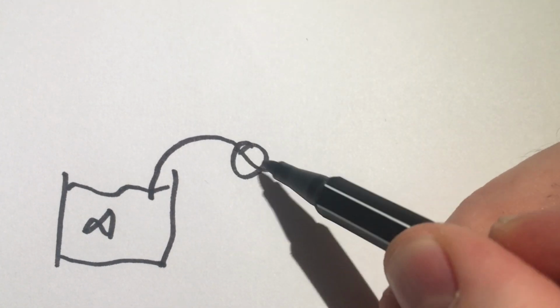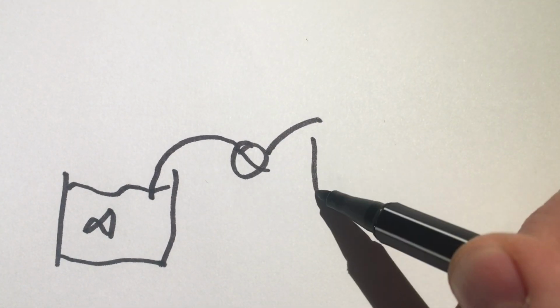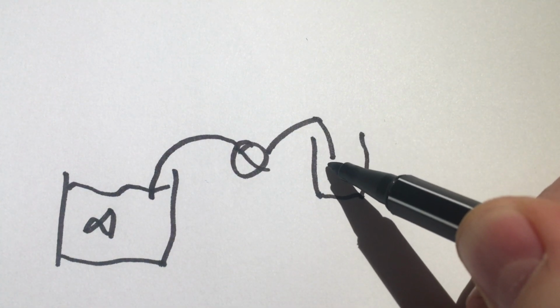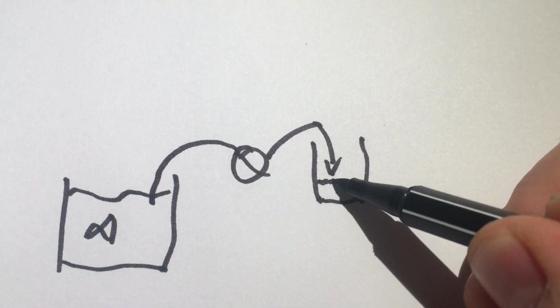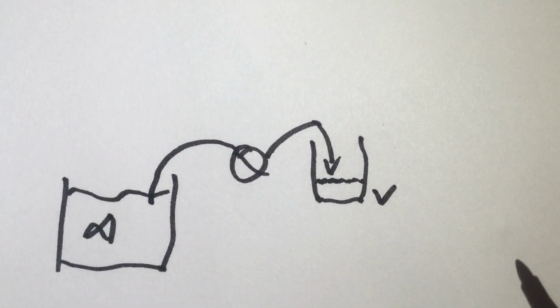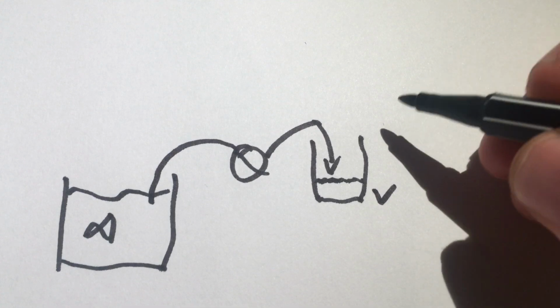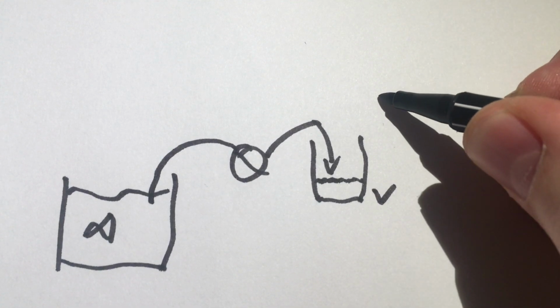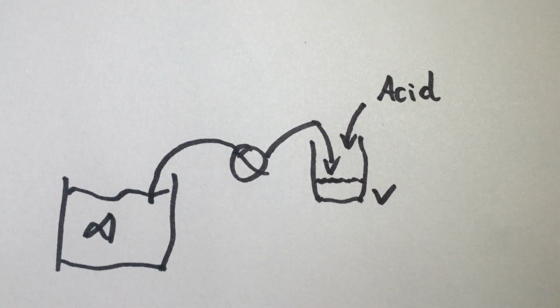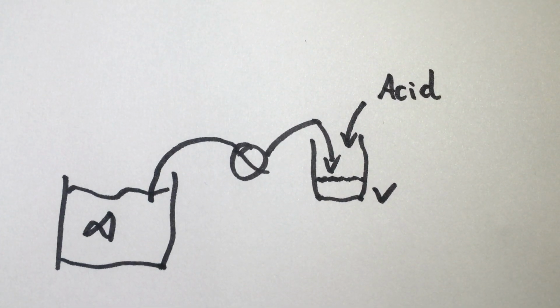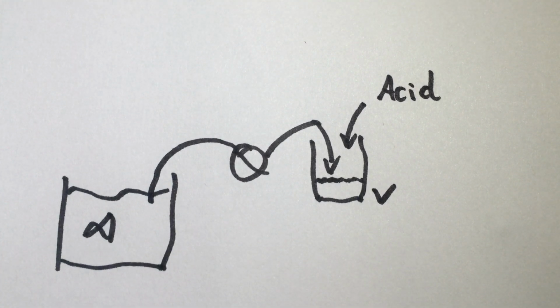So how do we do that? Well, the idea is that we take automatically a sample from the aquarium here, take the sample with some kind of pump and we put it into this cylinder. So we have here a water sample and we know the volume of this water sample. And to this water sample we add an acid, drop by drop. The smaller the volume we add at once, the better, because then we have a higher accuracy.